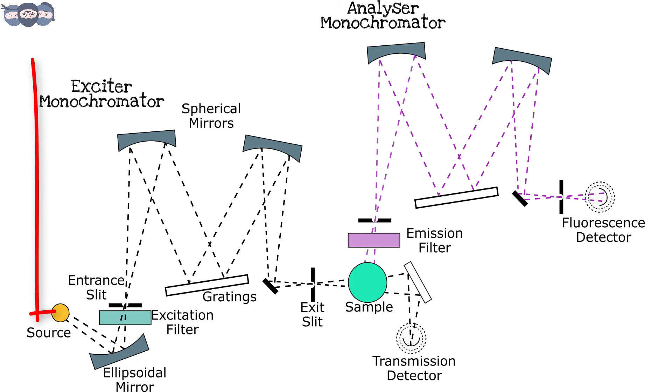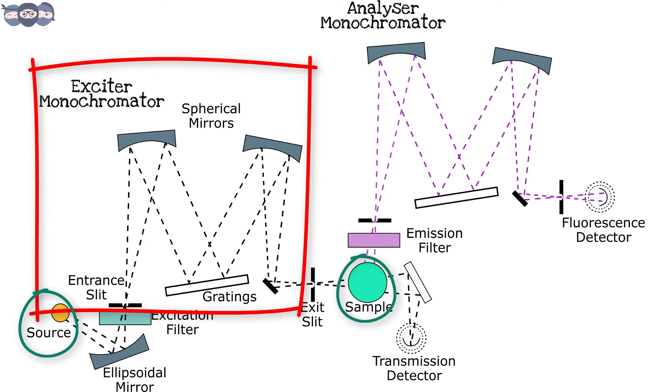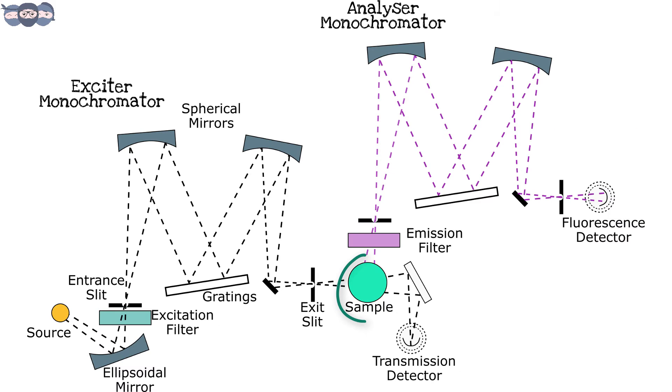The next component in the spectrofluorimeter is the exciter monochromator. This monochromator is placed between the light source and the cuvette which holds the sample. The exciter monochromator can be a prism monochromator or a diffraction grating. The sample under test is placed in the sample holder.